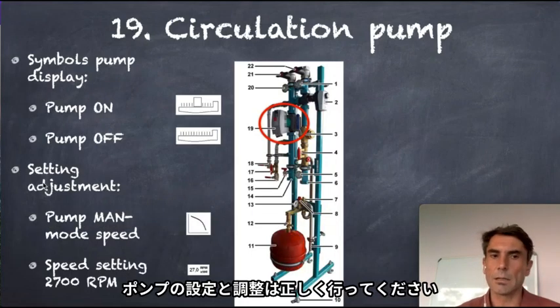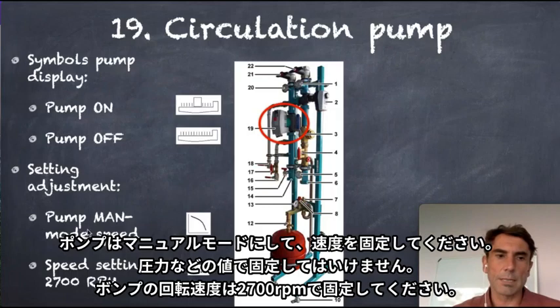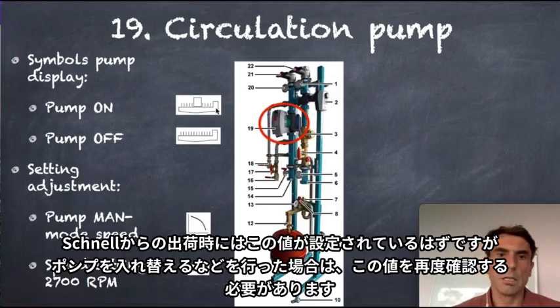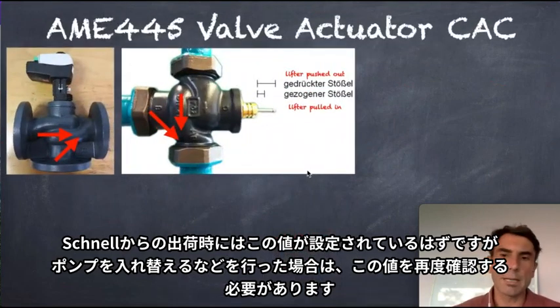The settings adjustment of this pump must be set to the right settings. One setting must be done: the pump mode must be on manual mode speed. That means we have a fixed ramp for a speed and it's not pressure controlled or something like that. And the speed must be adjusted to 2700 RPM in the pump. So usually, if you get the stuff from Schnell, the settings should be adjusted, but if we replace the pump or something, we always have to cross-check that the settings are right.